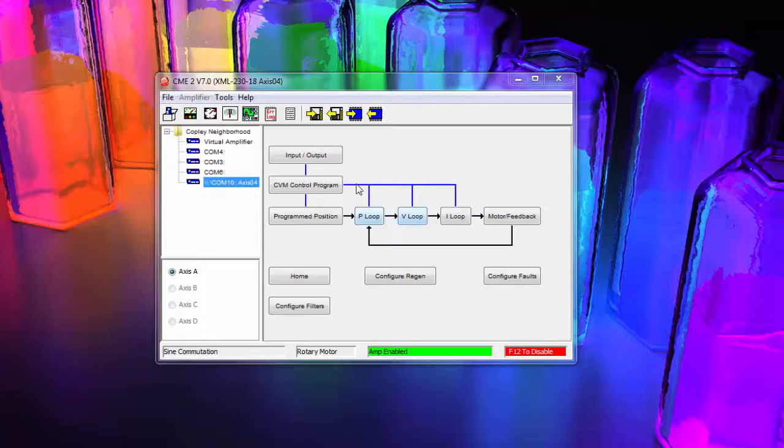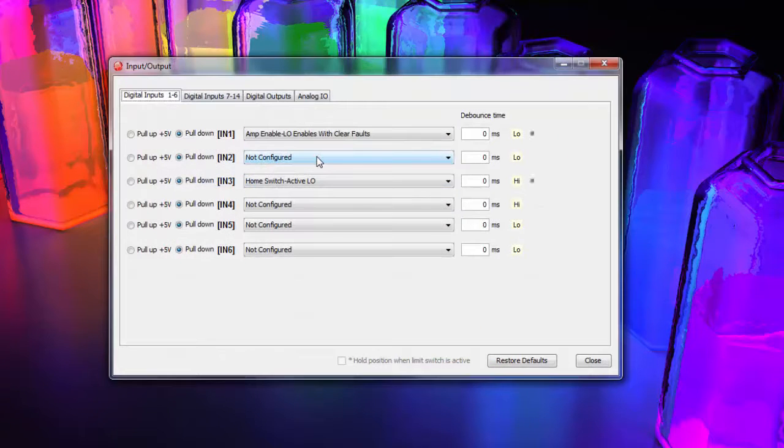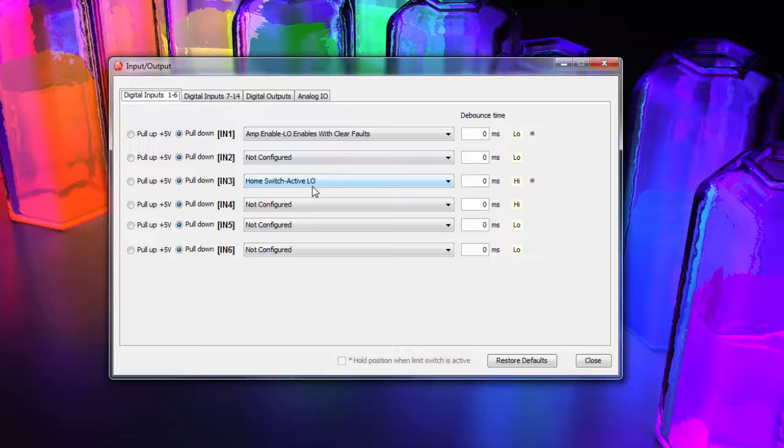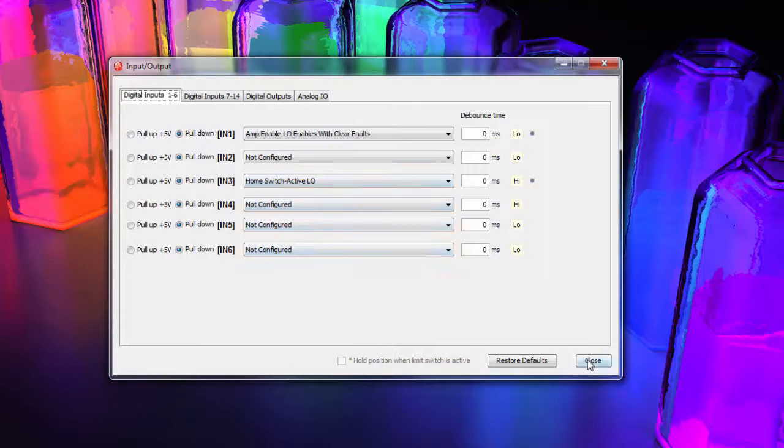Once wired, we configure the home switch input. In our case, we use input number 3. This input is PNP, so we select Pull Down. Finally, we are looking for it to be off to home, so we will select Active Low.